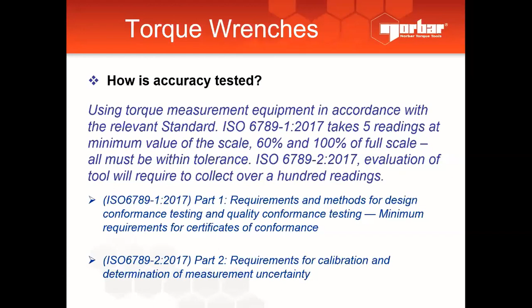Part 2 deals with measurement uncertainties, requiring you to collect over 140 readings. We won't go too in depth on that, but in short, ISO was revised in 2017 and differentiated into Part 1 and Part 2 — this is the standard we follow to test accuracy.